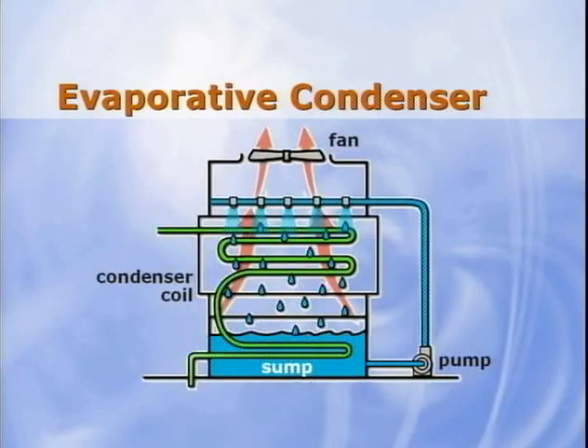Similar to an air-cooled condenser, refrigerant flows through tubes and outdoor air is drawn or blown over the tubes by a fan. The difference is that water is sprayed on the outer surfaces of the tubes. As the air passes over the tubes, a portion of the water evaporates. This evaporation process absorbs heat, causing the refrigerant vapor inside the tubes to condense into a liquid. The remaining water then gravitates into the sump, where it's recirculated by a high-flow pump.